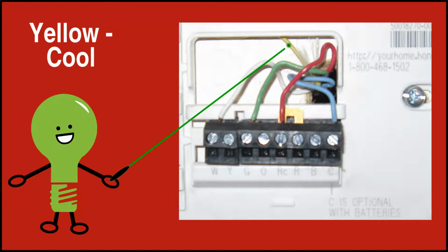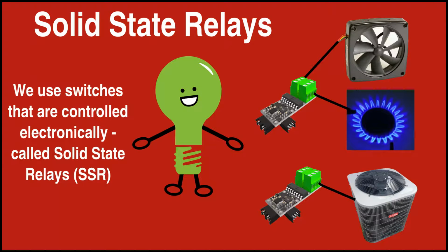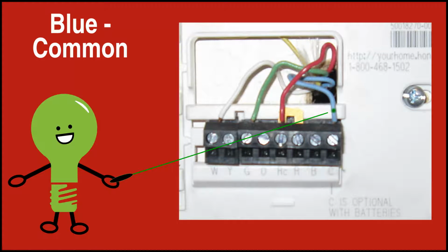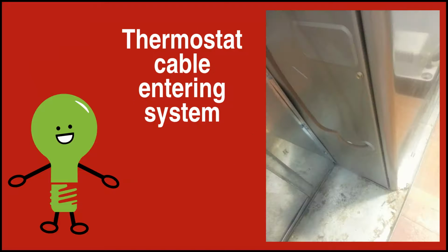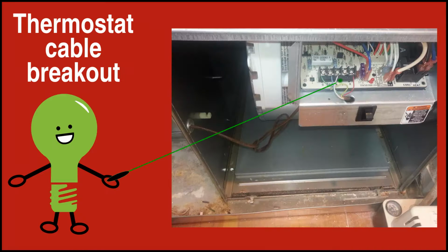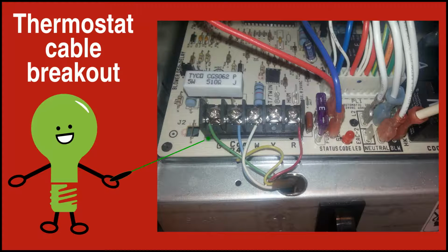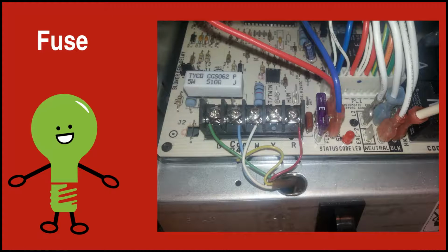The yellow wire is not used in this specific system, but in general controls a cooling element. If you live in a warm climate, you may use the yellow wire and not the white wire. And of course your system may use both, in which case you will need more than one SSR board. The blue wire is the common signal. It is used in conjunction with the red wire to supply a thermostat with power. Now let's look at the other end of the cable. You should be able to identify the thermostat wire going into your system. After removing a couple of covers, we can see where the thermostat wires are broken out of the cable and terminated. By the way, if you forget to turn off the power to the system and touch the red wire to the blue wire, this is the fuse you will blow.